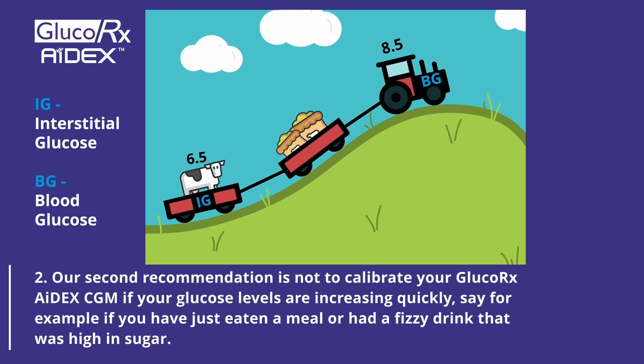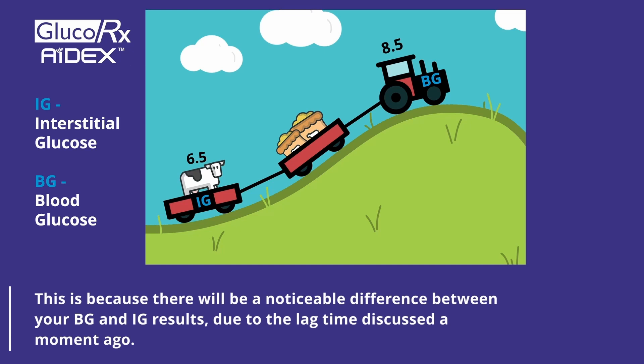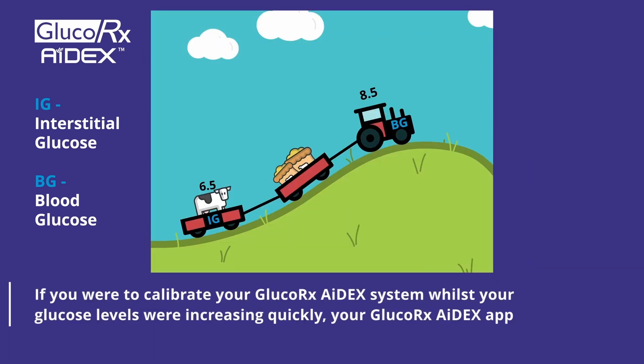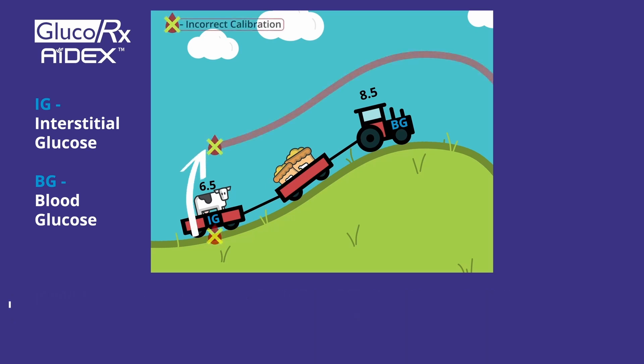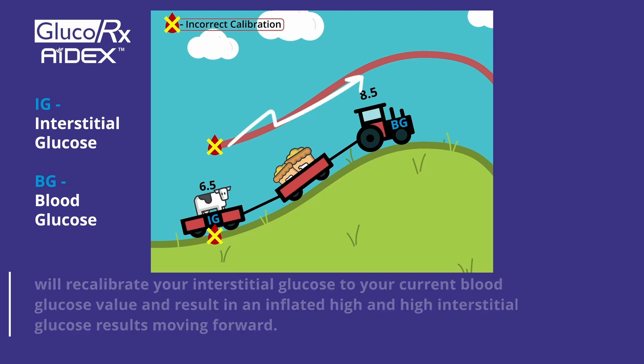Our second recommendation is not to calibrate your GlucoRx AiDEX CGM if your glucose levels are increasing quickly — for example, if you have just eaten a meal or had a fizzy drink that is high in sugar. This is because there will be a noticeable difference between your blood glucose and sensor glucose results due to the lag time discussed a moment ago. If you were to calibrate whilst your glucose levels were increasing quickly, your GlucoRx AiDEX app will recalibrate your sensor glucose to your current blood glucose value and it will result in inflated high sensor glucose results moving forward.